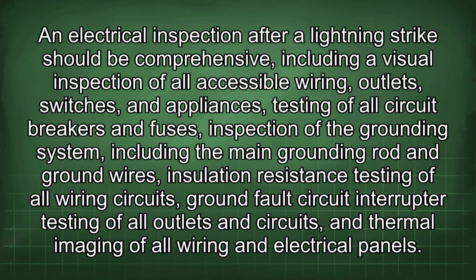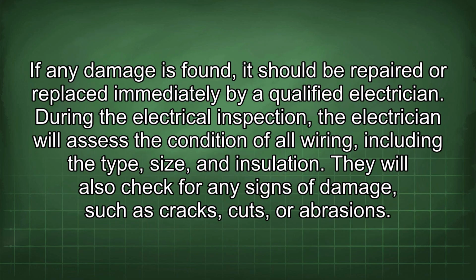An electrical inspection after a lightning strike should be comprehensive, including a visual inspection of all accessible wiring, outlets, switches, and appliances, testing of all circuit breakers and fuses, inspection of the grounding system, including the main grounding rod and ground wires, insulation resistance testing of all wiring circuits, ground fault circuit interrupter testing of all outlets and circuits, and thermal imaging of all wiring and electrical panels. If any damage is found, it should be repaired or replaced immediately by a qualified electrician.